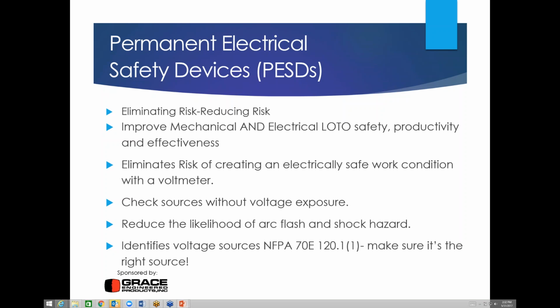So it also is very good at eliminating risks in creating an electrically safe work condition with a voltmeter, because you can see that not only has the source voltage disappeared, but as John also alluded to, the stored energy is a completely different type of energy that may exist. He had mentioned it may take as long as 5 minutes to dissipate, or longer depending on the source. The nice thing about the PESDs, or some of them, is it does bleed down that stored energy. And we'll talk a little bit more about that in just a few slides.